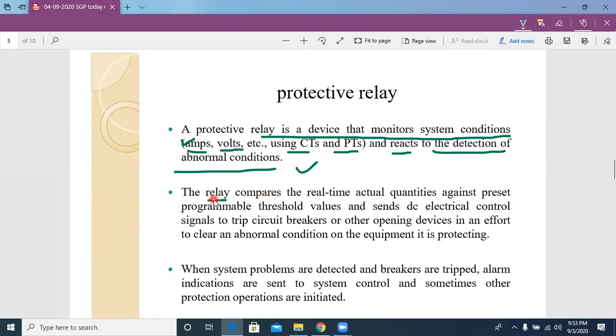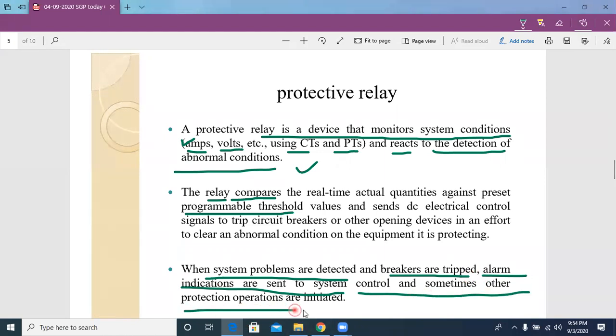One more important thing is, the relay always compares the real current value with its preset value. When a difference happens between these two values, ultimately it sends a signal to the circuit breaker. When the system problems are detected, the breakers are tripped and alarm indications are sent to the system control, and sometimes other protection operations are initiated. So when the circuit breaker gets a signal from the relay, the circuit breaker contacts open, and the faulty section is isolated from the healthy one.